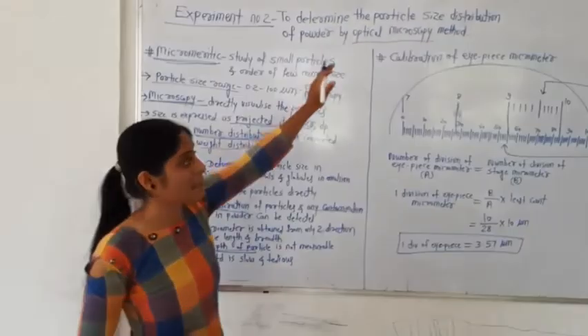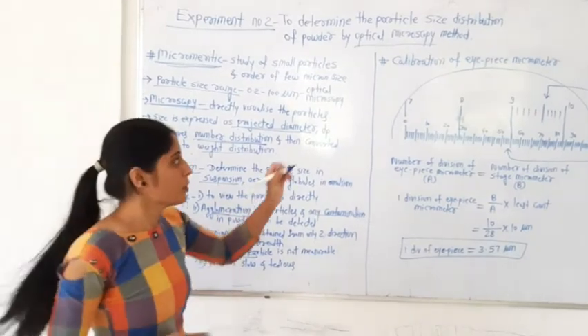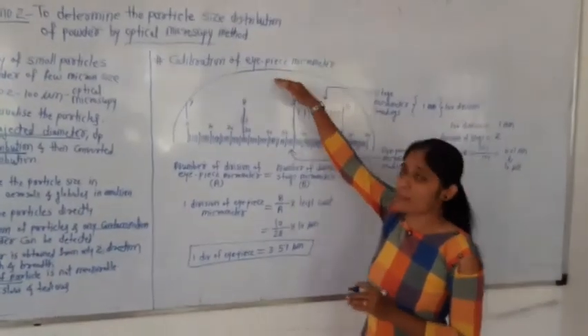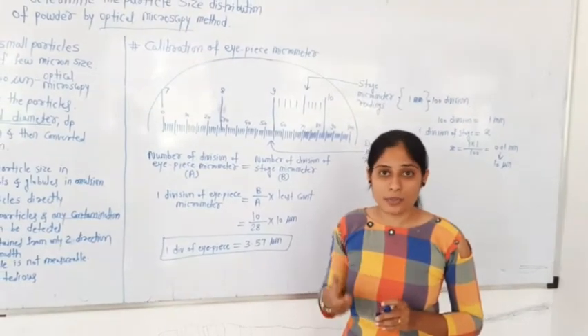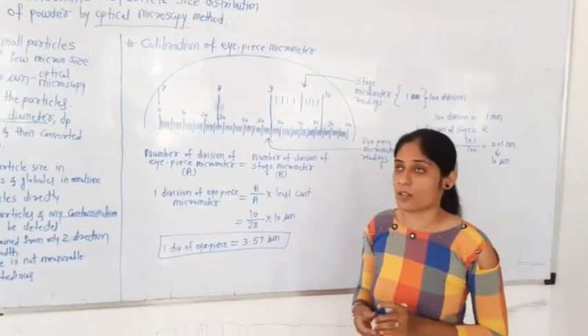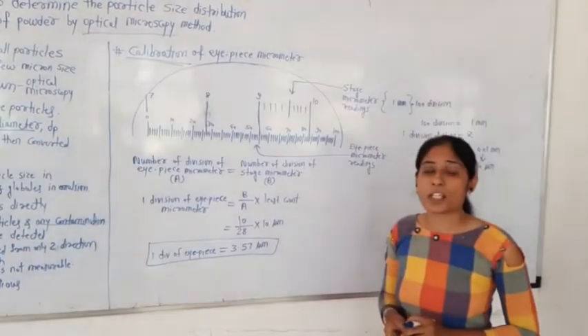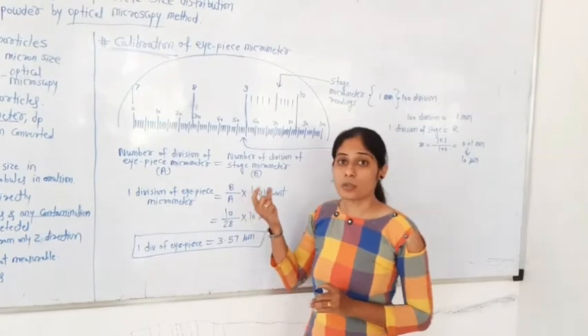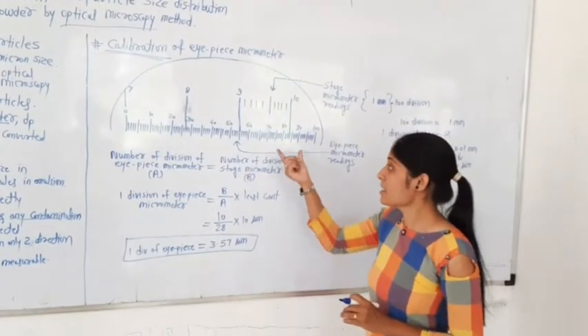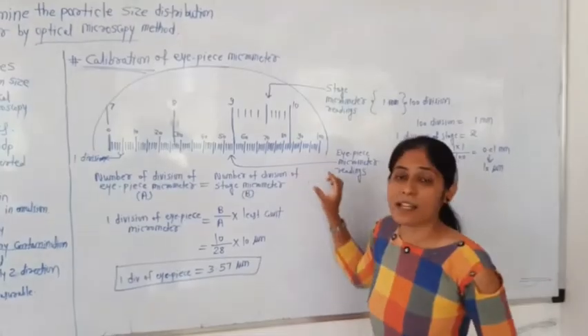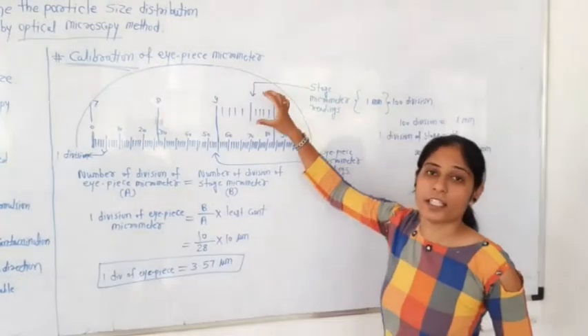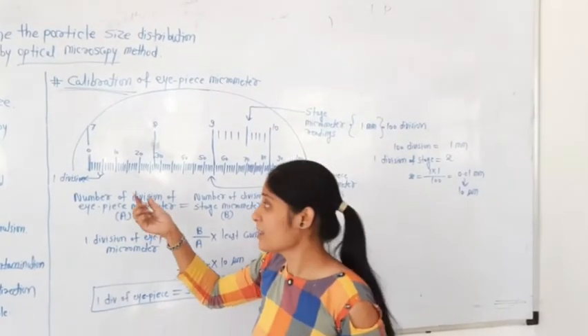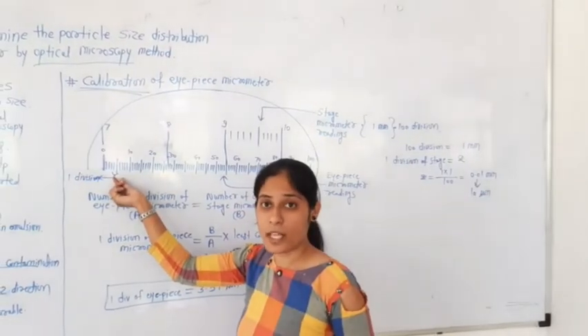For determination of particle size and particle size distribution, the first step of the procedure is calibration of the eyepiece micrometer. We use the eyepiece micrometer to determine the particle size, so before using it we must calibrate it. Calibration means determining the actual length between the two lines, or the actual length between two divisions.